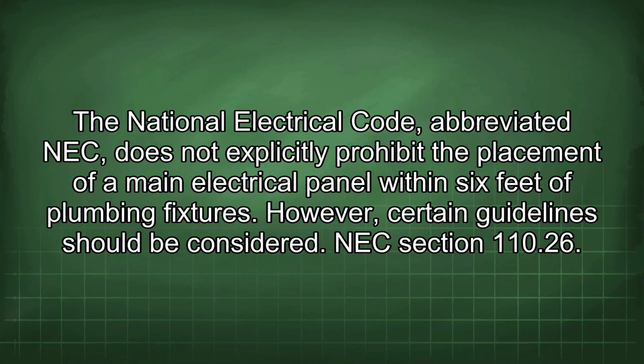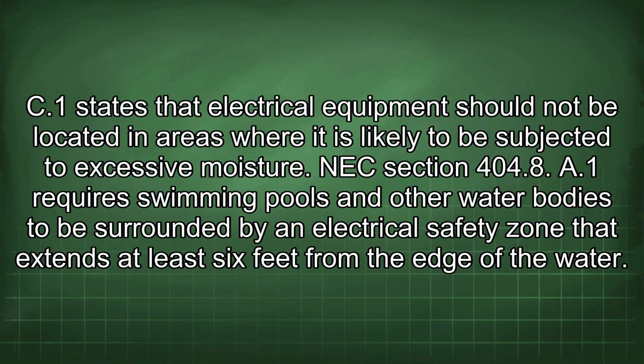The National Electrical Code, abbreviated NEC, does not explicitly prohibit the placement of a main electrical panel within 6 feet of plumbing fixtures. However, certain guidelines should be considered. NEC Section 110.26 C1 states that electrical equipment should not be located in areas where it is likely to be subjected to excessive moisture.